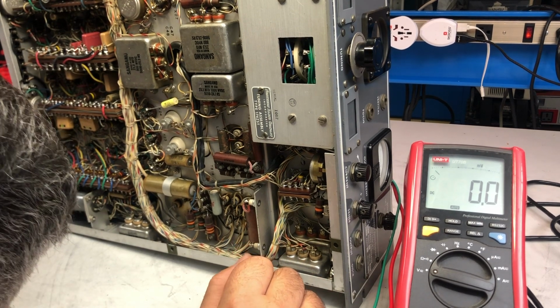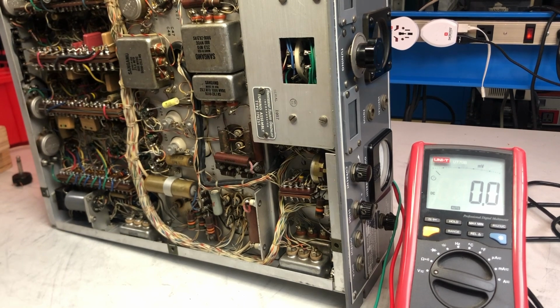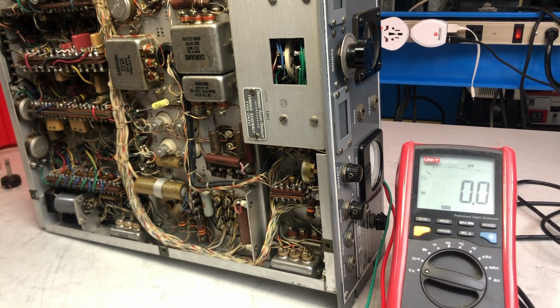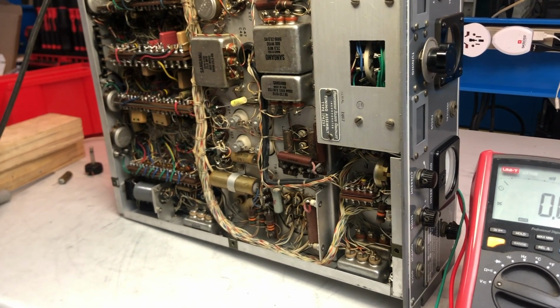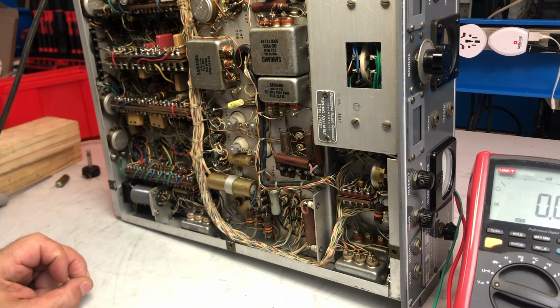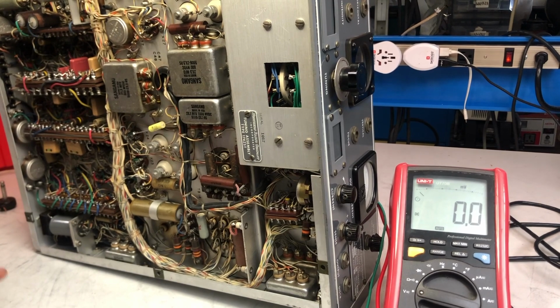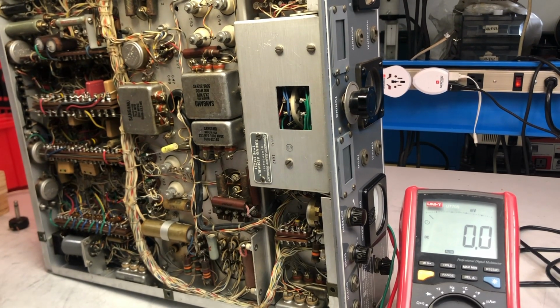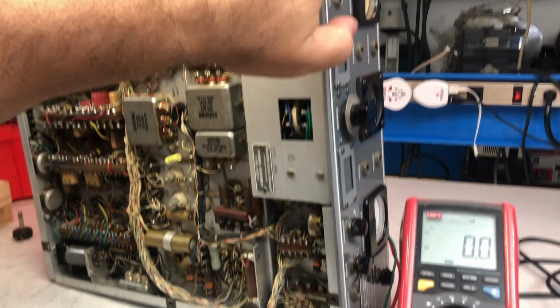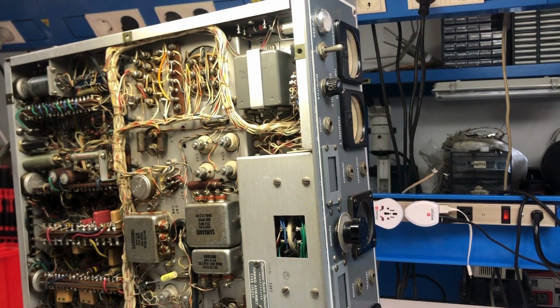I'm at 35 volts. I will rise up slowly and I'll be back as soon as I have some live sign, if any. By the way, I have already performed the basic checks like the fuse rating, and it's okay. And with the ohmmeter, checking if the primary section of the transformers have continuity, and they have, so everything looks okay. Oh, by the way, I have the power switch off, so I need to go back.